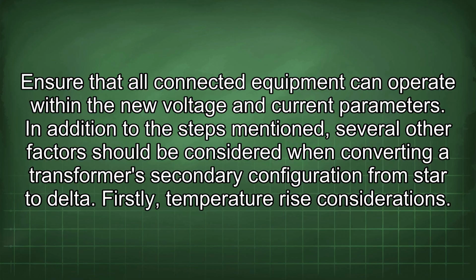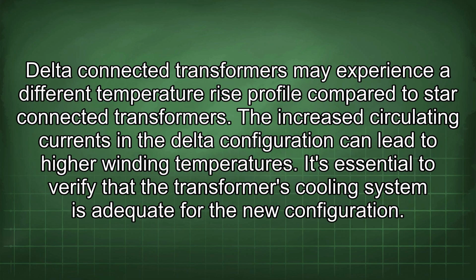In addition to the steps mentioned, several other factors should be considered when converting a transformer's secondary configuration from star to delta. Firstly, temperature-rise considerations. Delta-connected transformers may experience a different temperature rise profile compared to star-connected transformers. The increased circulating currents in the delta configuration can lead to higher winding temperatures. It's essential to verify that the transformer's cooling system is adequate for the new configuration.